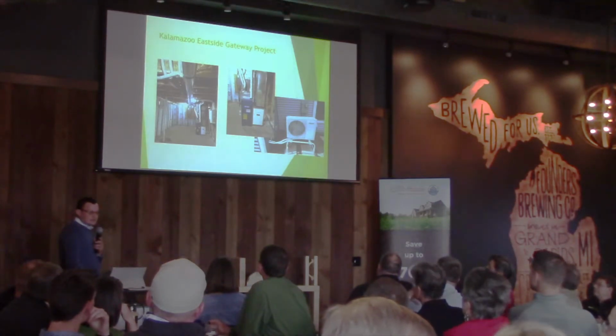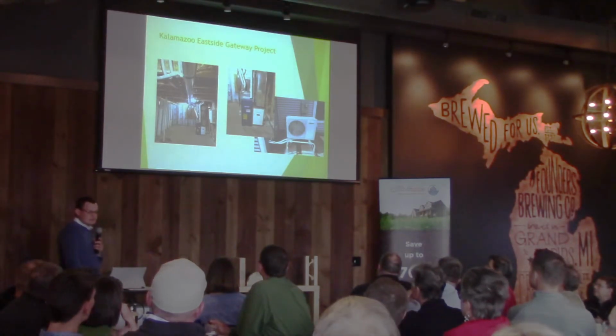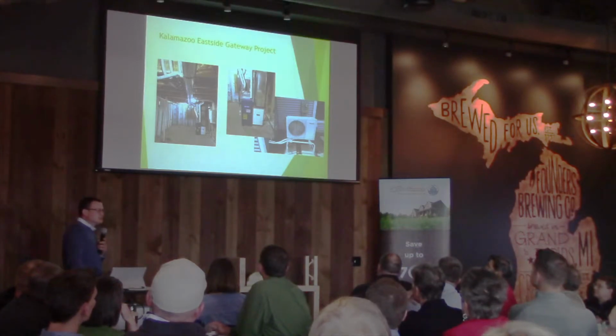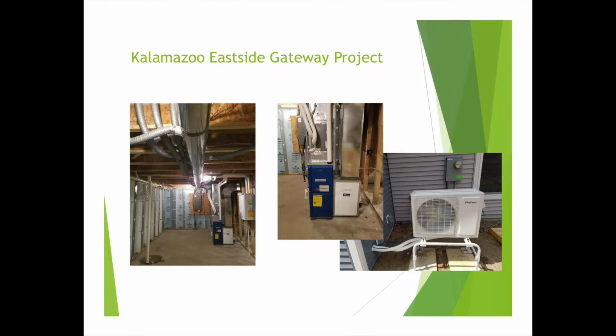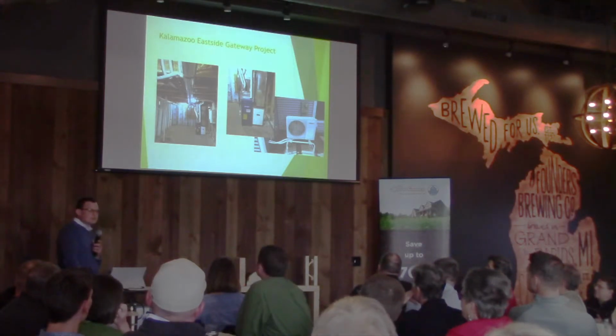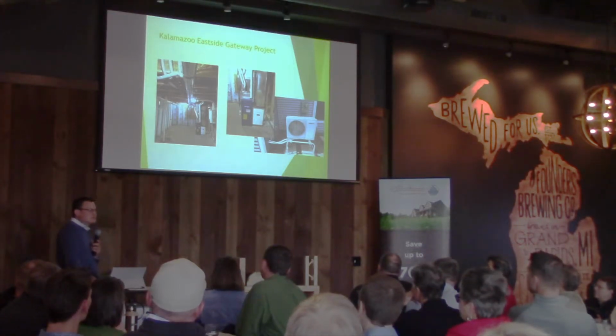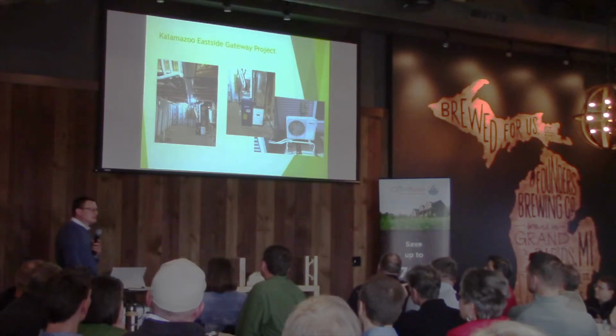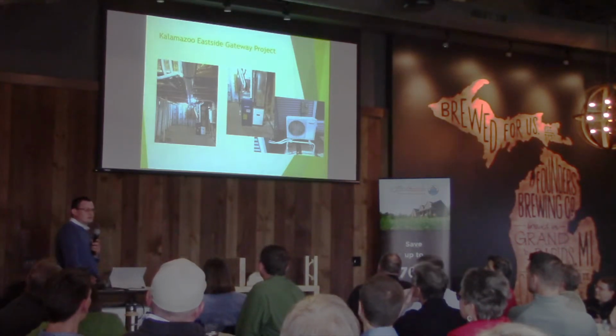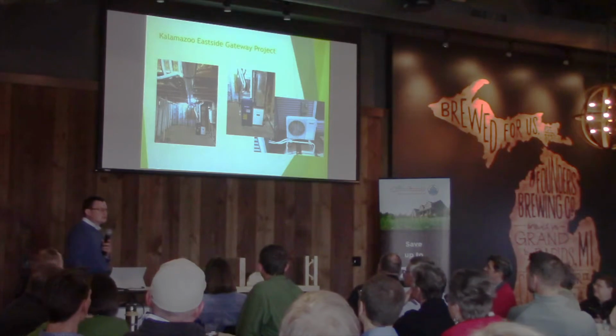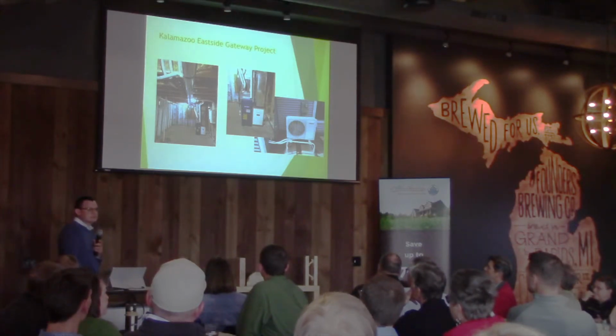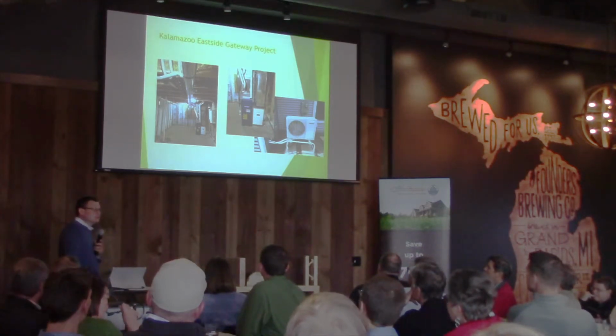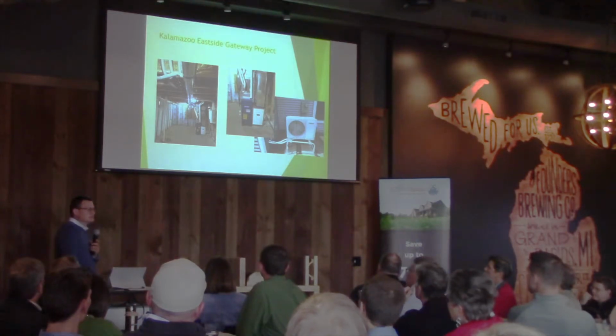This is the air handler in the basement and the outside unit. If you notice, the outside unit looks like a mini split compressor, because it is. Dettson took that and tied it into an indoor A coil—a standard air conditioner coil, the same one Lennox uses, but they pulled the piston out of it. Then they did a bunch of engineering and some software writing, made some control boards to make everything talk to each other, and created a really efficient ducted whole house heat pump system that's as efficient as any multi-head mini split or ducted mini split I've seen.